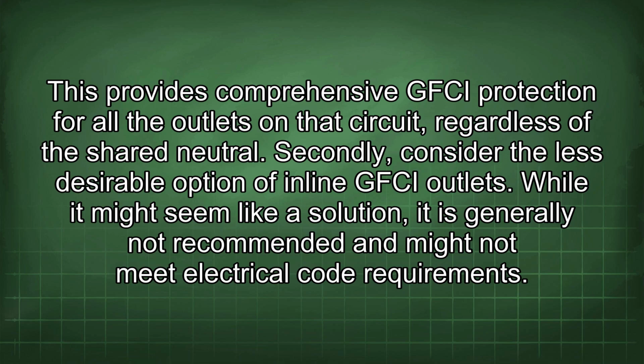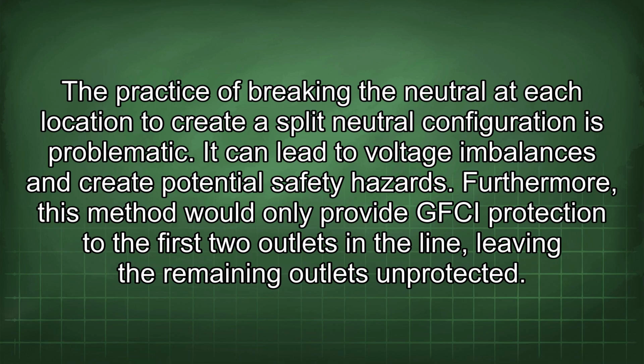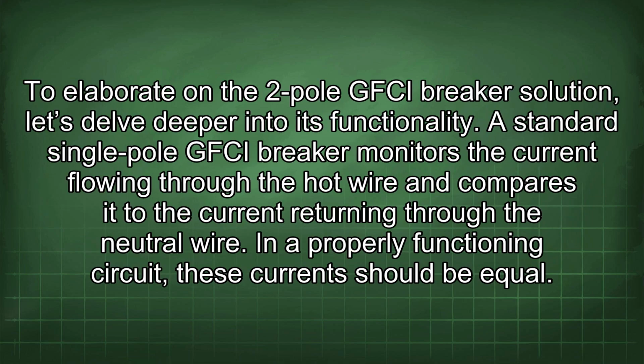Secondly, consider the less desirable option of inline GFCI outlets. While it might seem like a solution, it is generally not recommended and might not meet electrical code requirements. The practice of breaking the neutral at each location to create a split neutral configuration is problematic. It can lead to voltage imbalances and create potential safety hazards. Furthermore, this method would only provide GFCI protection to the first two outlets in the line, leaving the remaining outlets unprotected. To elaborate on the two-pole GFCI breaker solution, let's delve deeper into its functionality.